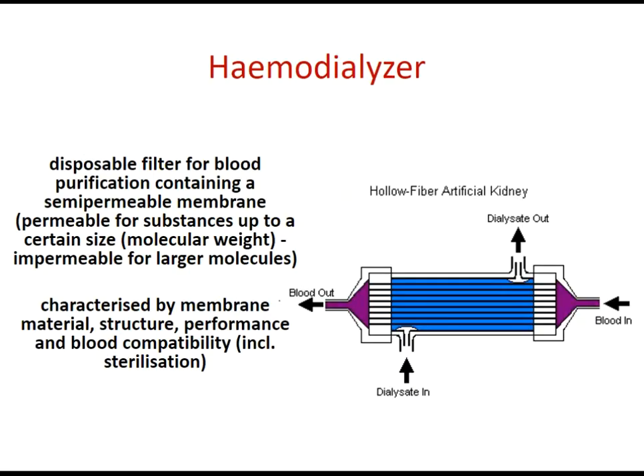The device for dialysis is the hemodialyzer, a disposable filter for blood purification containing a semi-permeable dialysis membrane. It is permeable for substances up to a certain molecular weight, and impermeable for larger molecules like albumin. It is characterized by membrane material — nowadays all synthetic — the structure, and the performance: either low-flux or high-flux membrane. Blood compatibility and sterilization type are also key characteristics.